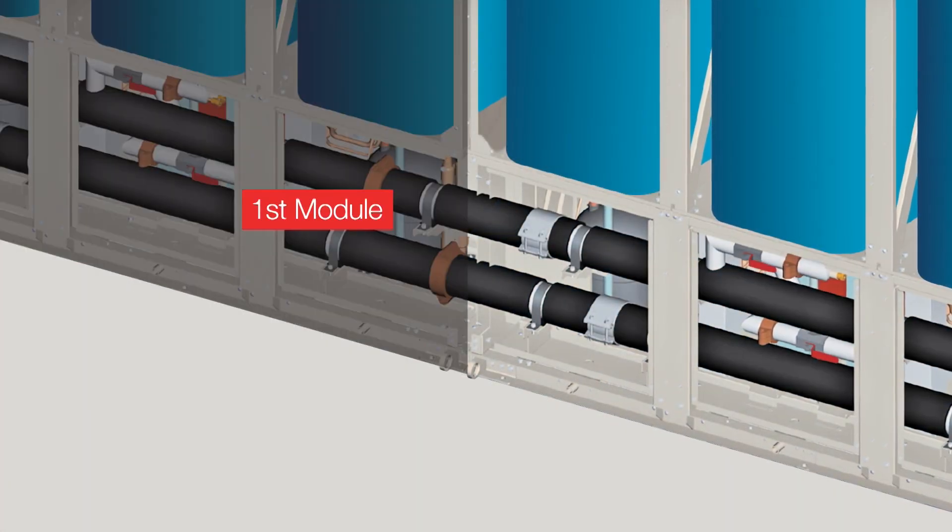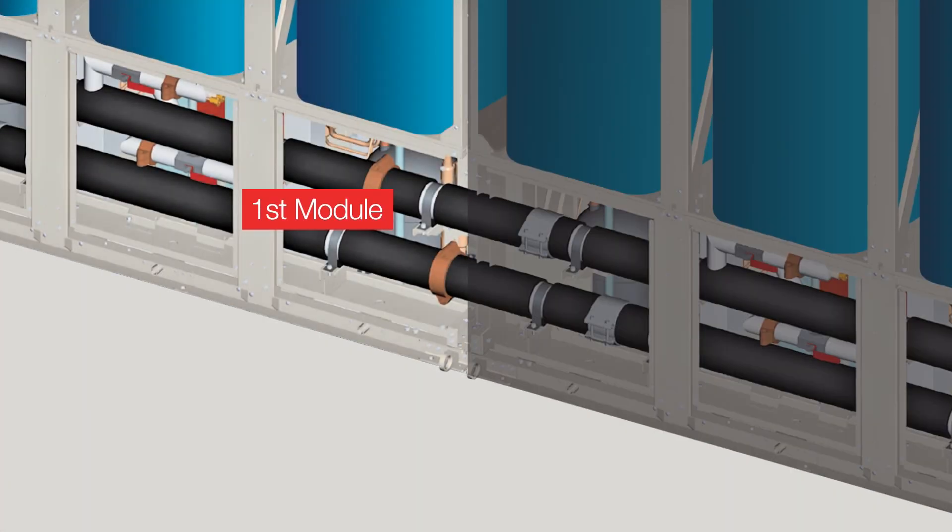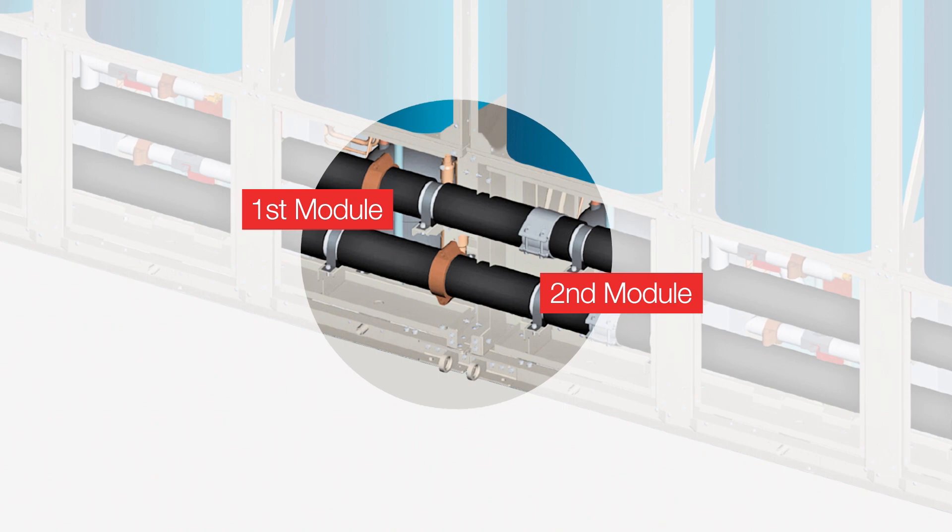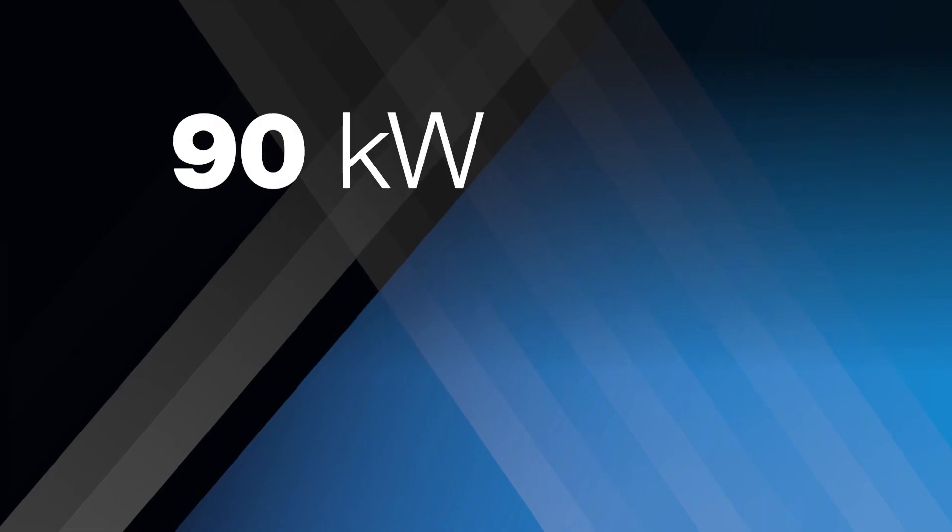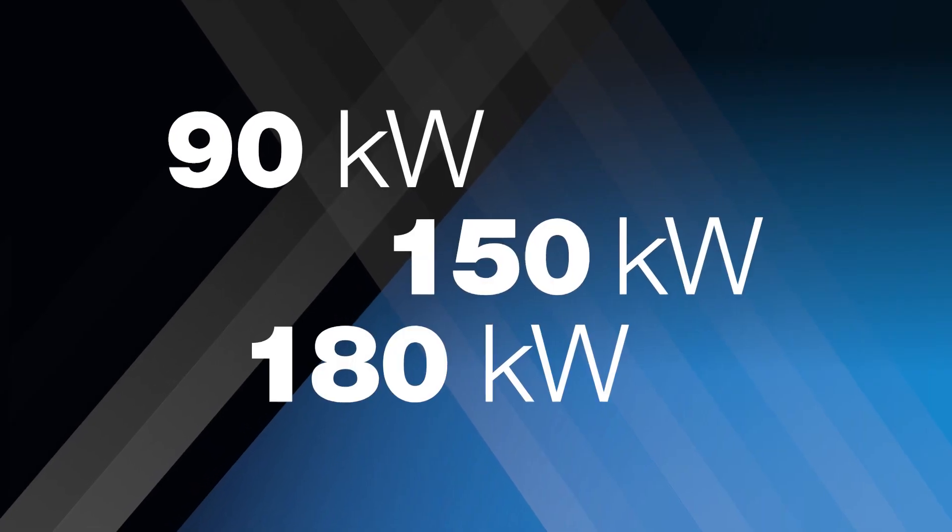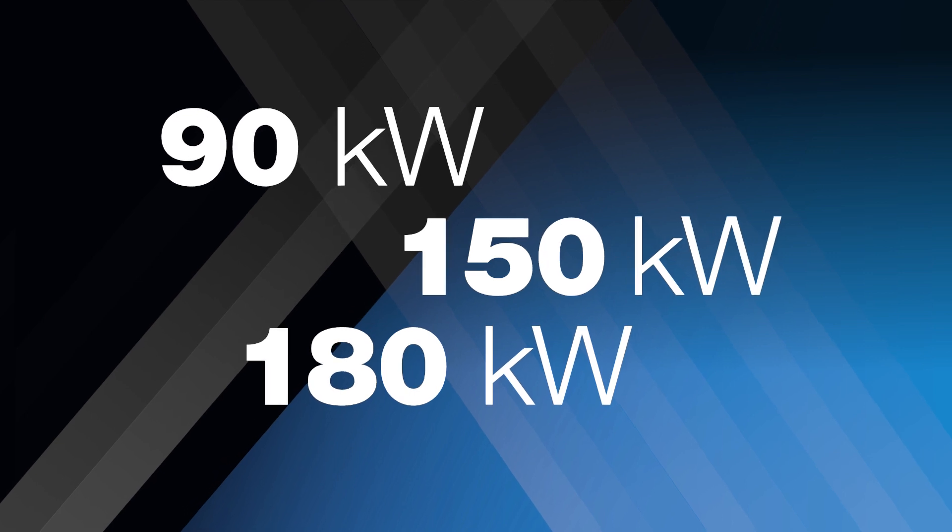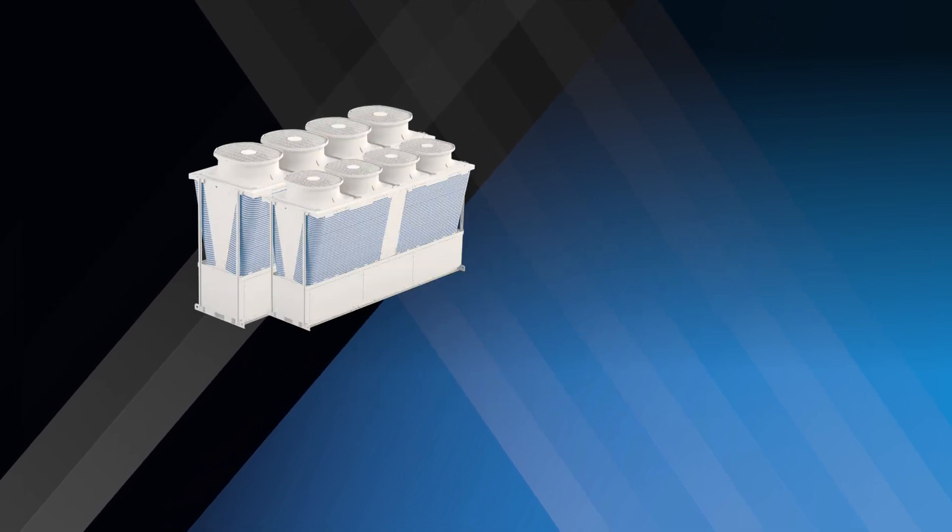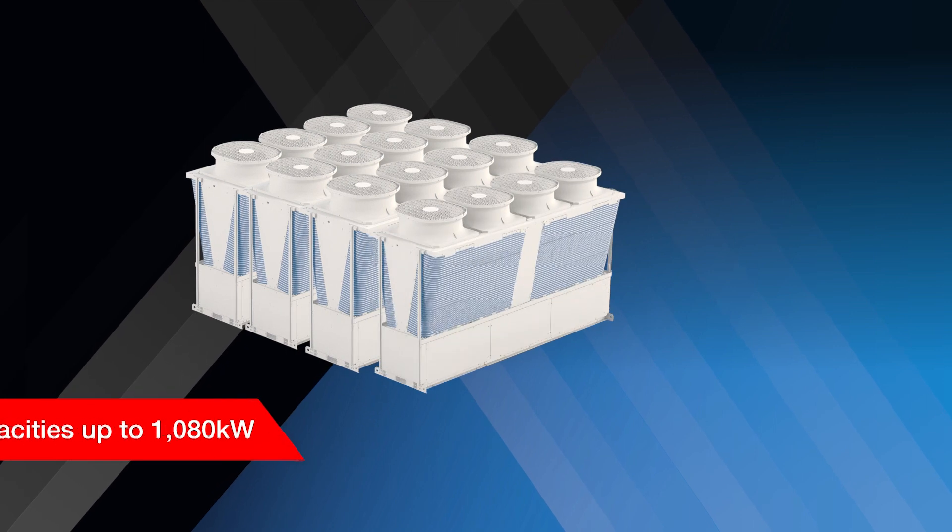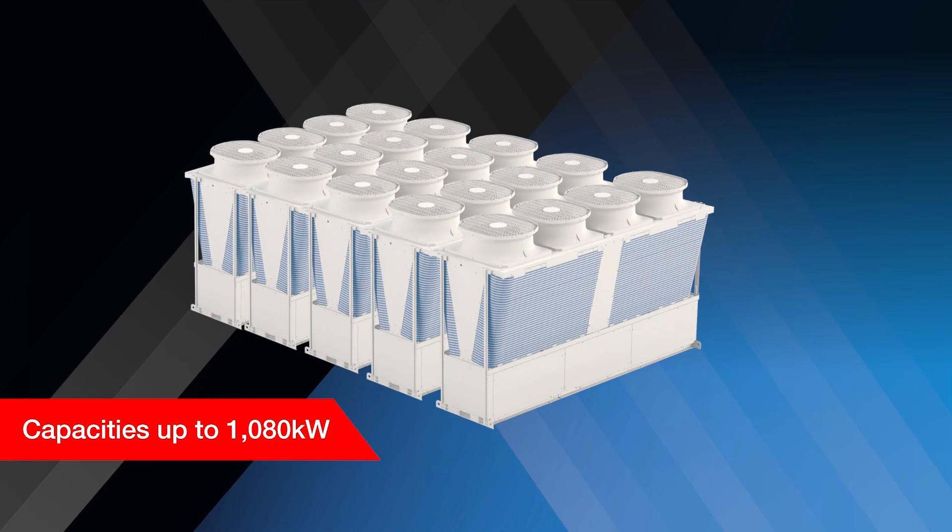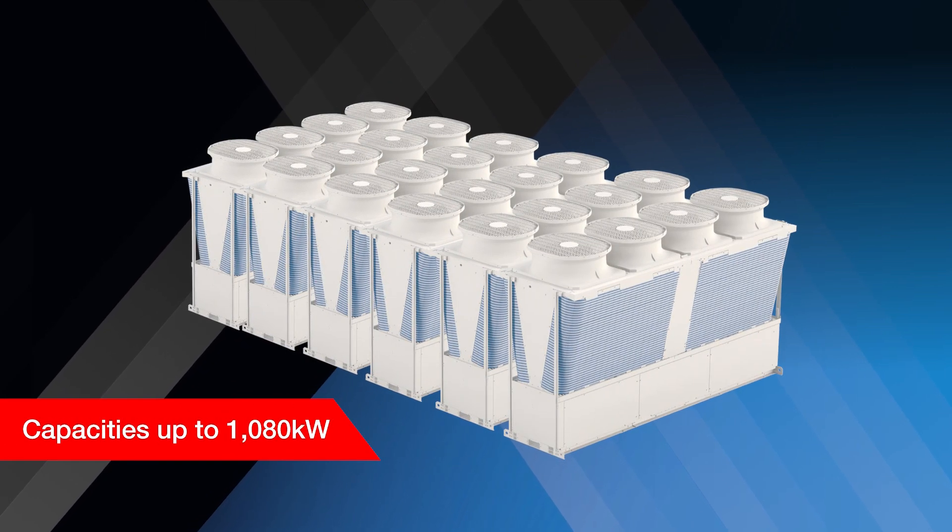With market-leading low noise levels, they are easy to integrate systems with built-in internal header pipes. The E-Series is available in 90, 150, and 180 kilowatt modules, and as many as 6 units can be connected to provide a capacity of up to 1080 kilowatts.